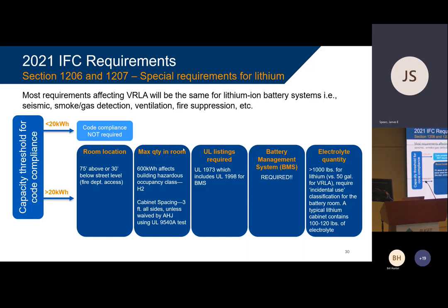The maximum lithium quantity in a room is 600 kilowatt hours. So that sounds like a pretty high limit if each cabinet is only 34 kilowatt hours. But if I've got 3 large UPSs with 6 battery cabinets on each one, and they're all in the same room, that's over 600 kilowatt hours of battery, and that requires a special hazardous occupancy class, special construction of the room, etc. Again, can be waived. How do you get these things waived? Now, you use that UL 9540A test report that says no propagation of flames.